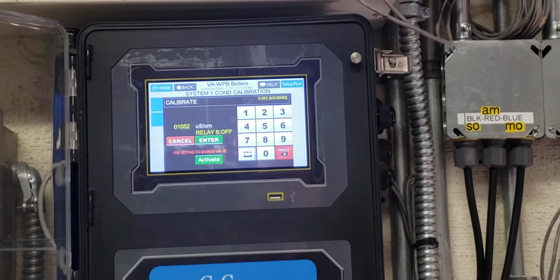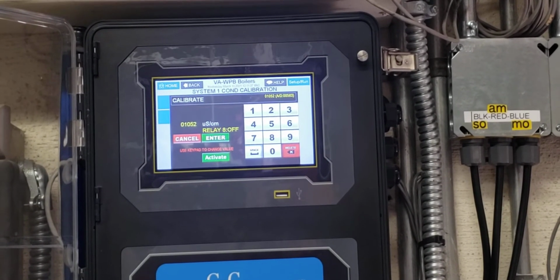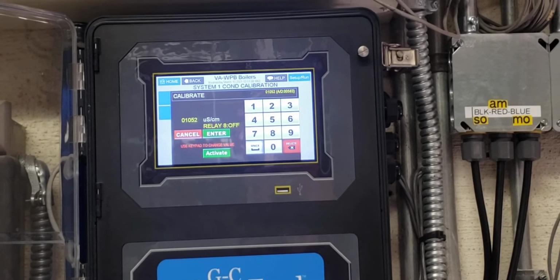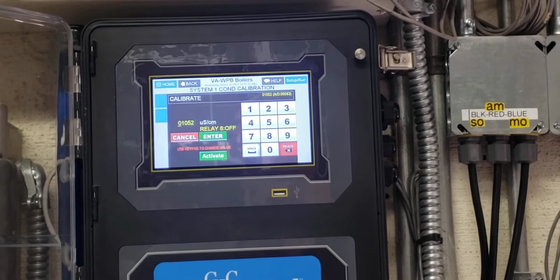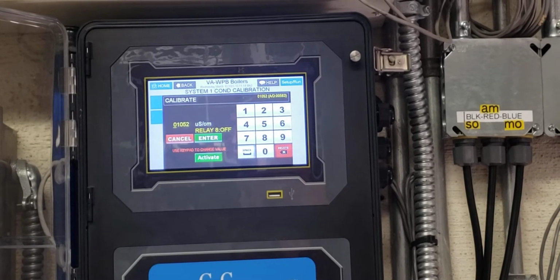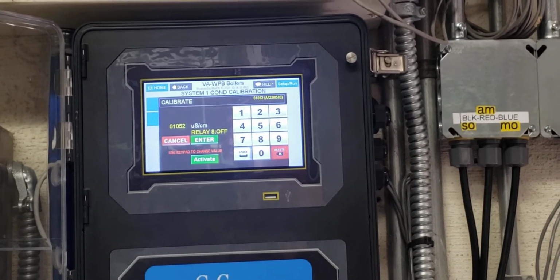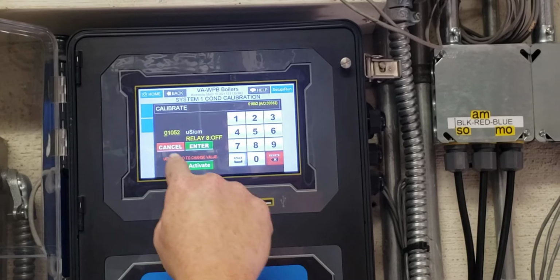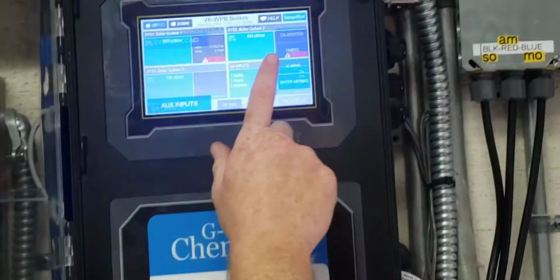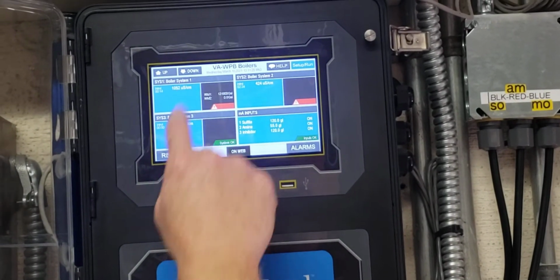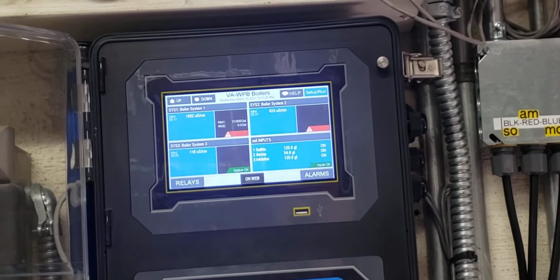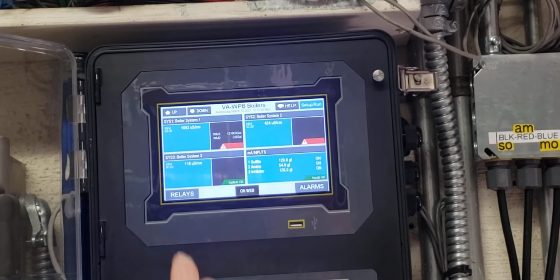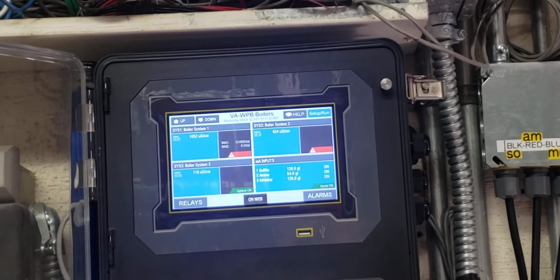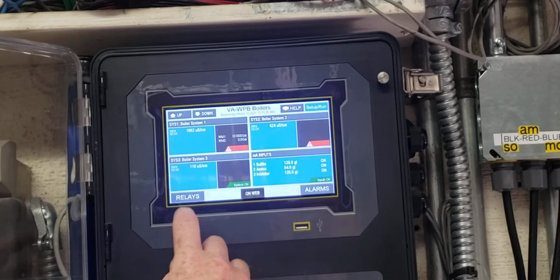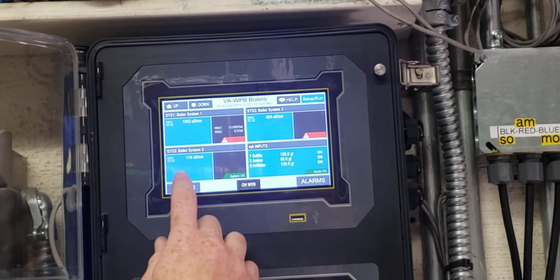Now, something important to do: if it hasn't been blowing down, then you can manually open up the relay. Let's go over that first. If the conductivity reading is way off from what you got, let's just say, we'll do it on boiler 3 because it's not running right now. Let's just say we got 516 instead of 116.